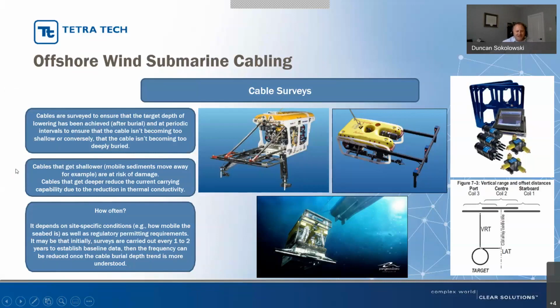Cables that get shallower, for example due to mobile seabed sediments, mean that the cable's at risk of damage, and also that the cable could risk anyone else using that piece of the seabed, such as the fishing industry. If the cable gets deeper, what that means is the ampacity is reduced, so it can't dissipate heat as effectively, and you can't run the same current down the cable—it can't take as much electricity, for want of a better word. So you want to bury the cable deeply enough that it's protected, but not too deeply, otherwise you might not be able to take the whole output of the wind farm down it electrically.